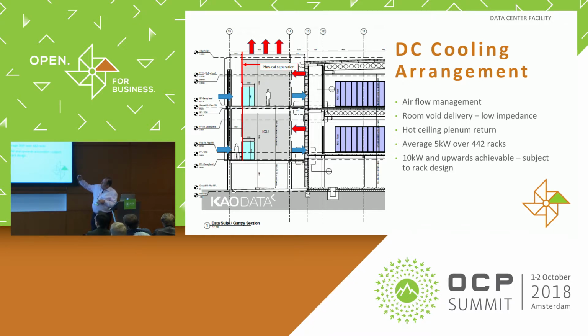What we do is effectively have a fan wall. So you can probably see a sort of corridor here where we blow air from the units out on a gantry at the side of the facility. That has a perforated wall so that we equalise the pressure along there and allows air to then filter into the complete room void. So it's very low velocity, unhindered in where it goes. So effectively we just allow the servers to draw air from that sort of bathtub of nominally 24-degree air and then go through into the hot aisle. We then capture the hot air and return it through a ceiling void back to where the red arrow goes out to the external equipment.